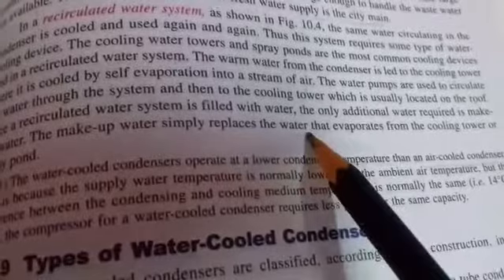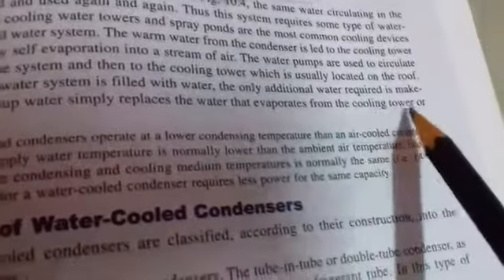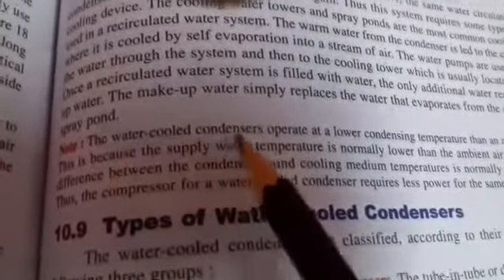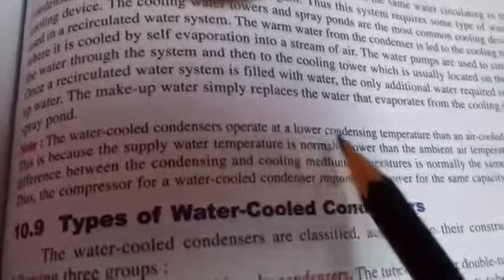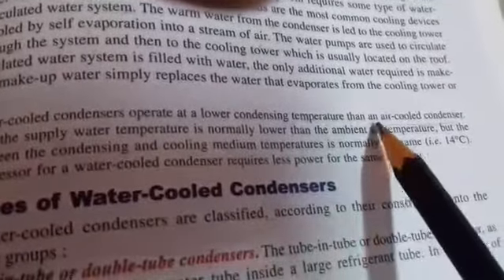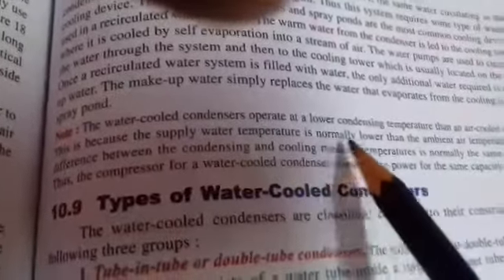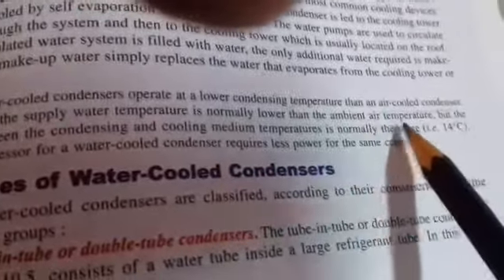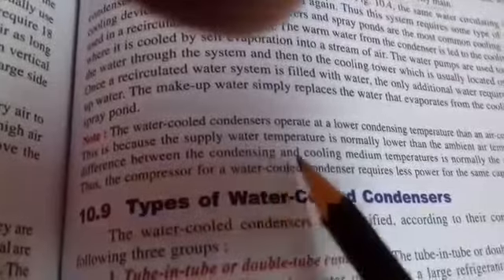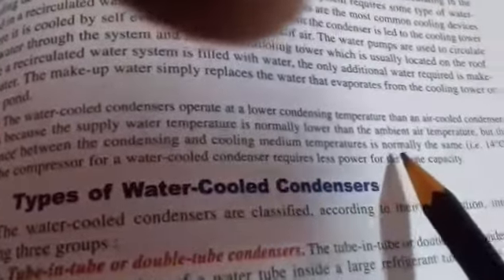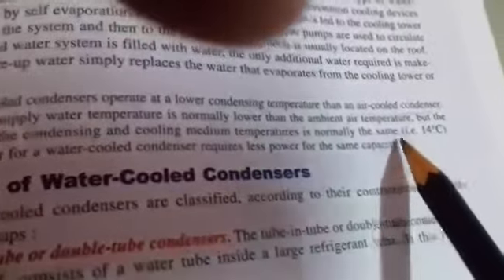Now notice the water cooled condensers operate at a lower condensing temperature than an air cooled condenser. This is because the supply of water temperature is normally lower than ambient air temperature, but the difference between the condensing and cooling medium temperature is normally the same. Thus, the compressor for a water cooled condenser requires less power for the same capacity.